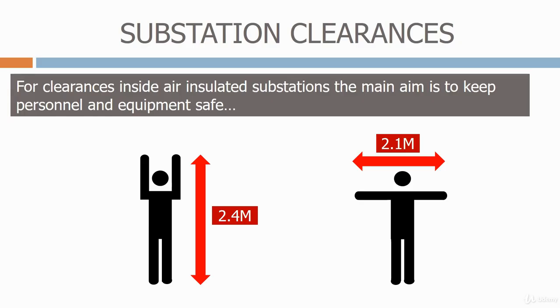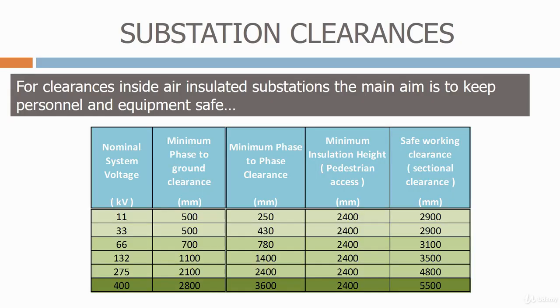Let's now look at a typical utilities table of electrical clearances. As you would expect, as the system voltage increases, all of the electrical clearance distances also increase. In the first two columns, we have the minimum phase-to-ground clearance and the minimum phase-to-phase clearance. These are purely design clearances and are used to define the minimum distances between the electrical equipment. The next column is the minimum insulation height, which is the distance to the bottom of the insulator. This is based on the 2.4 meter reach of a typical person.